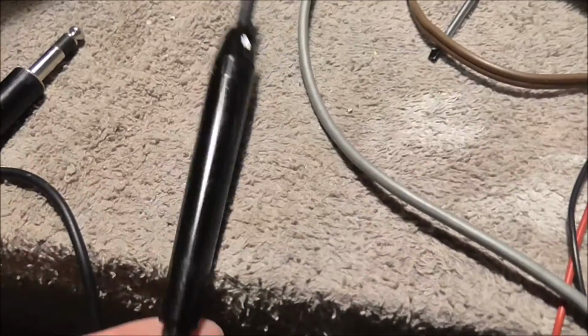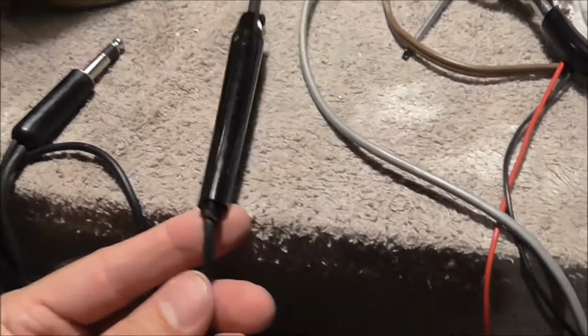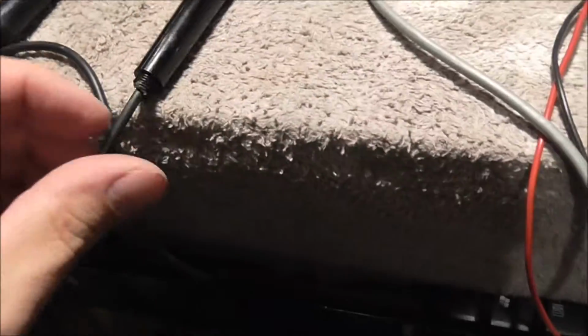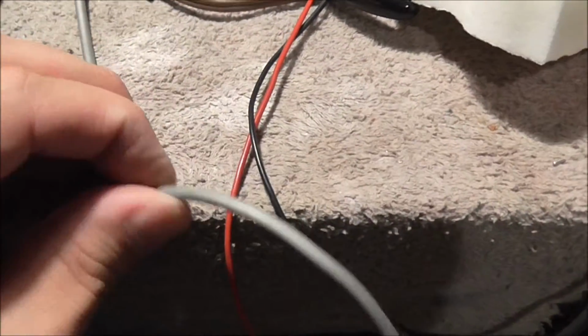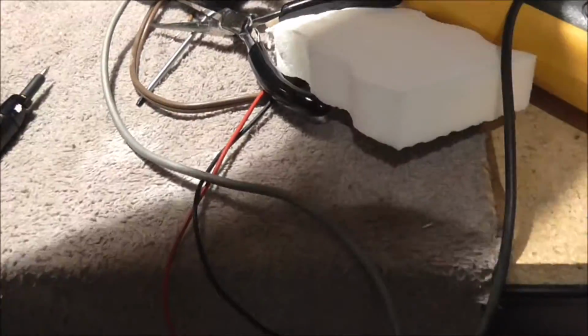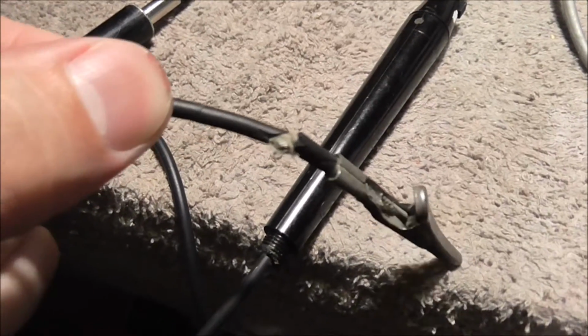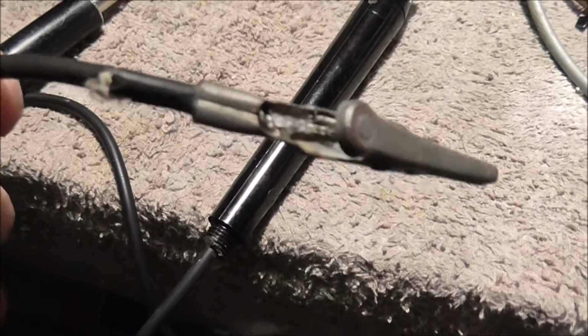Anyway, I changed out the wire on this probe because I was having a lot of problems with the other wire, and I think it had some breaks inside of it, so I changed that. And the next thing I'm doing here, as I mentioned earlier, is I actually need to replace or do something with the clip on this end. You see how there's a bunch of breaks in the wire here? It's still electrically conductive, but it's not safe either way.